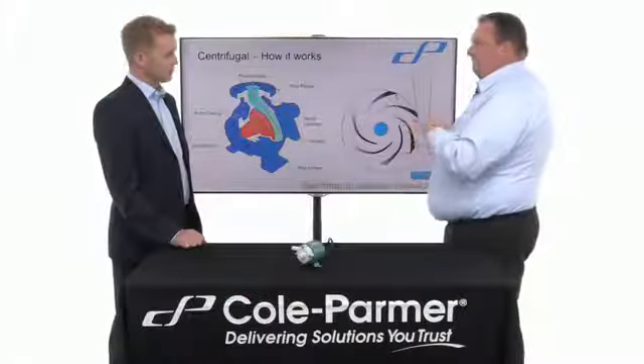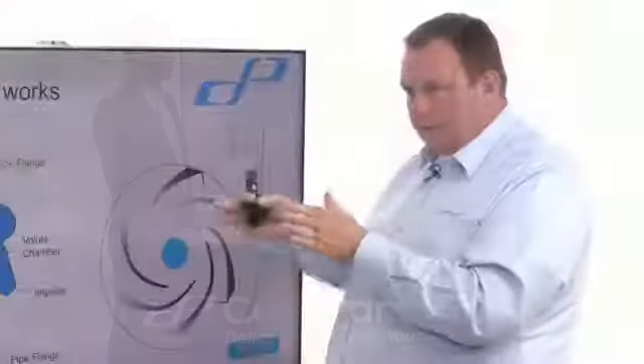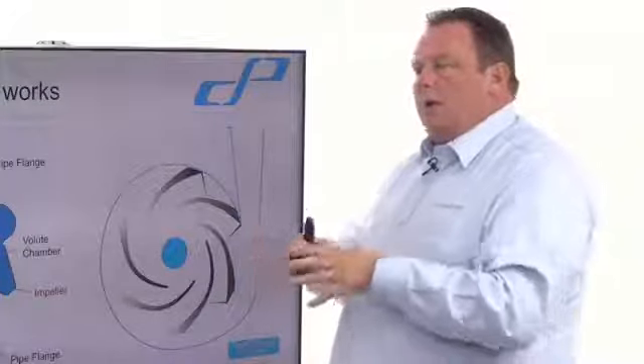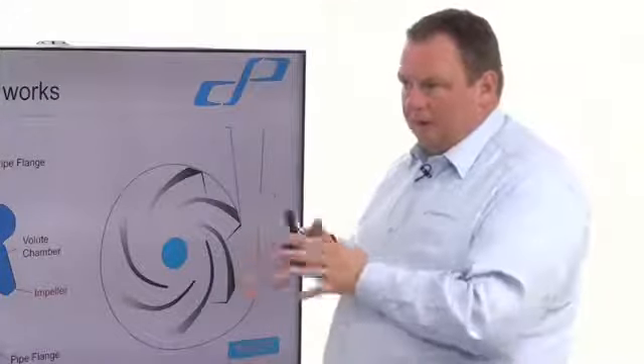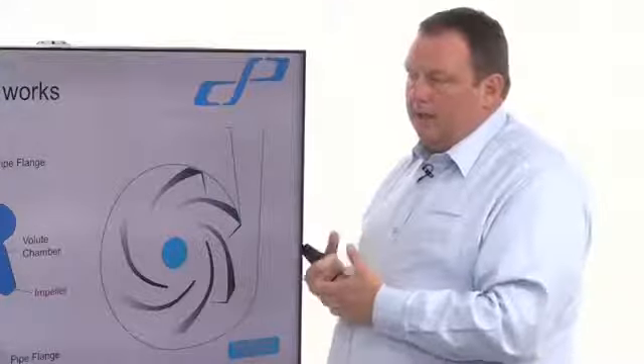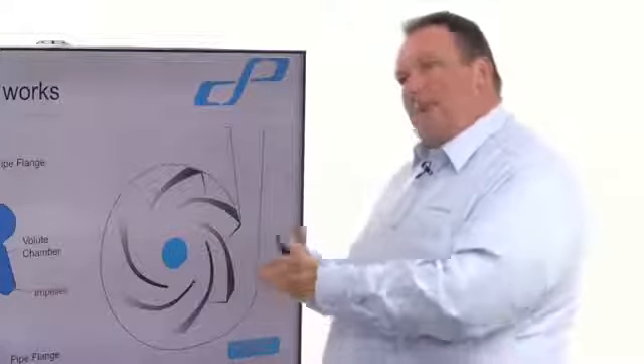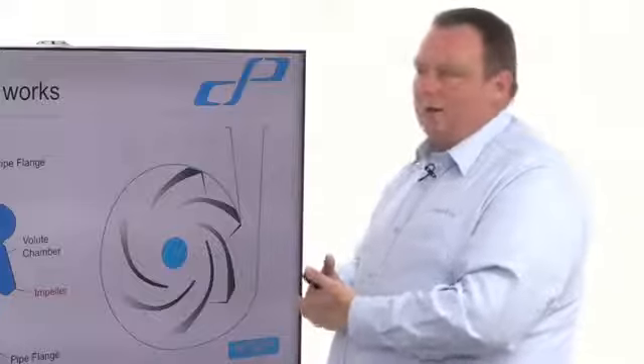So there's different variants with different sizes of impeller. And then you can adjust that to make your flow rate greater or smaller. Some companies will even trim the impeller for you to make it specifically. Another good thing is they tend to be factory tested, so on the larger ones you'll have things that are already tested before they come out, so they say it already works.